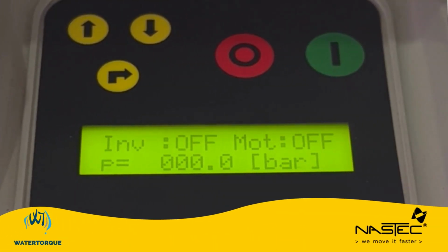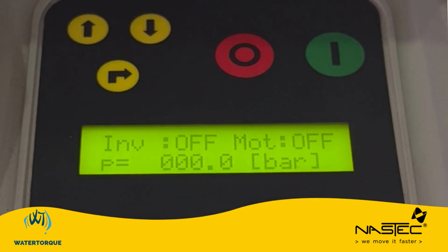Today we are setting MPPT mode on a Nastec 4HS 0504 via the CM module. So the first step we need to ensure is that the Inv is off and MOT is off. That indicates that both motor and inverter are off. If we don't do this step, we'll be able to access the menu, but we won't actually be able to change any of the parameters.